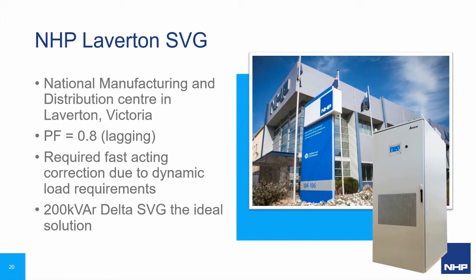So given the continuously changing load requirements on our site, a solution was required that would respond dynamically to a wide range of power factor issues. So for us, the Delta SVG was the perfect option. So we've put in a 200 kVAR model. So the SVG itself has minimal maintenance requirements, and the modular nature of the unit made installation easy, and the capacity can be expanded in the future as we require it.